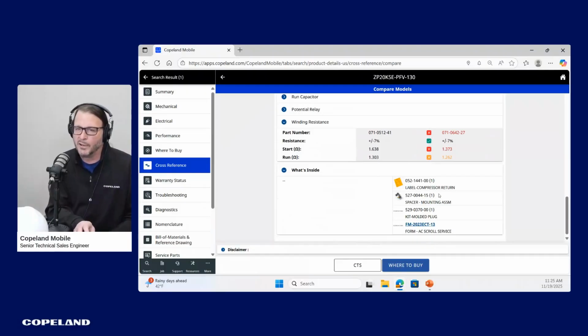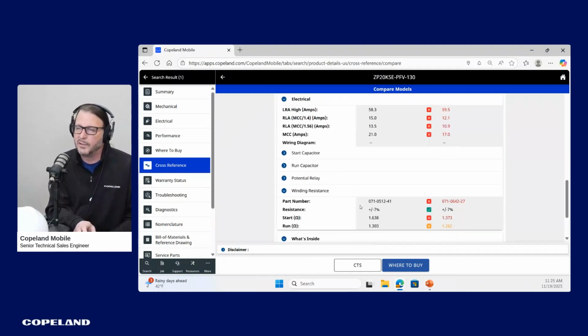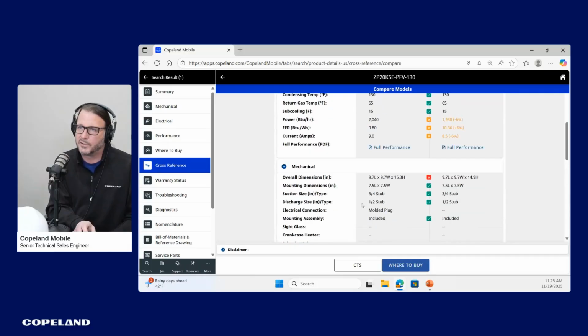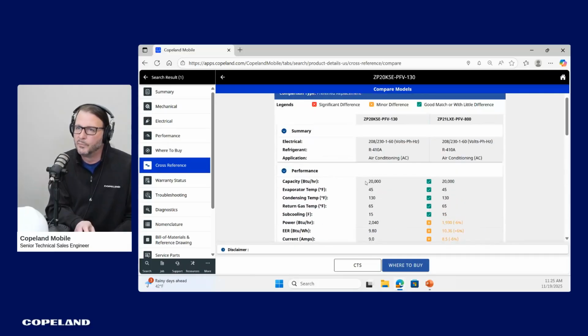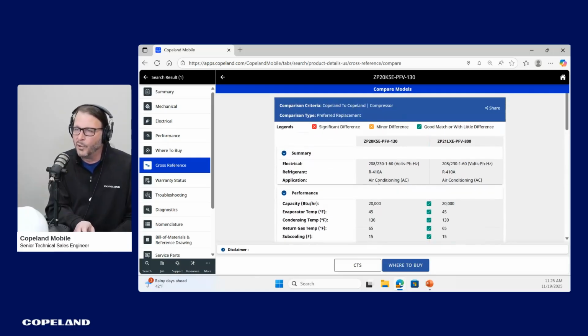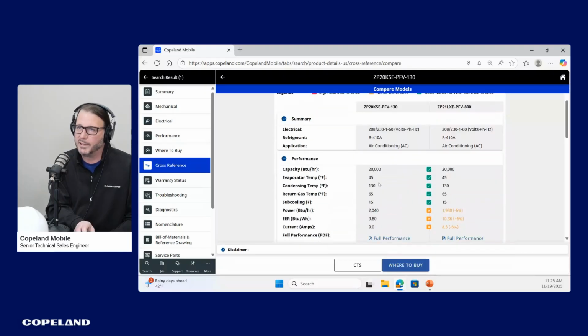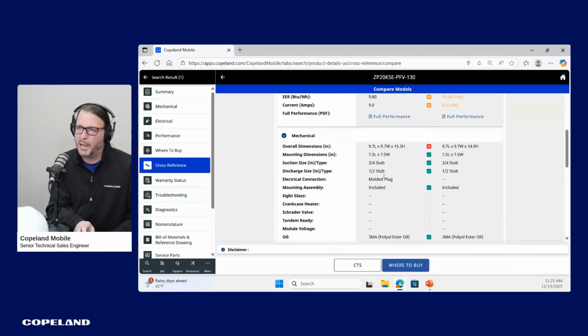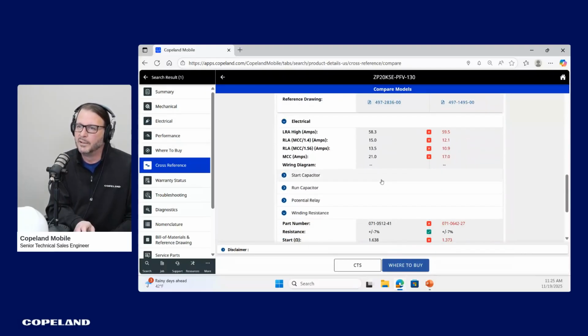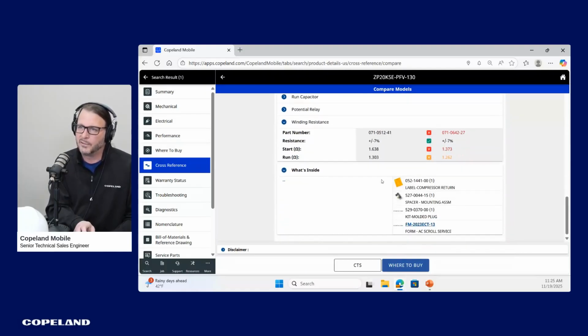They're actually not meant to go on and off several times, so it's a good thing you're getting a new one there. That's a successful cross. What I want to point out is it's not just a cross on capacity, where this thing pumps exactly the same way as the old compressor. I call this a multi-point cross, where I'm looking at capacity, mounting, and electrical information. That's what I consider a good cross, not just one point.